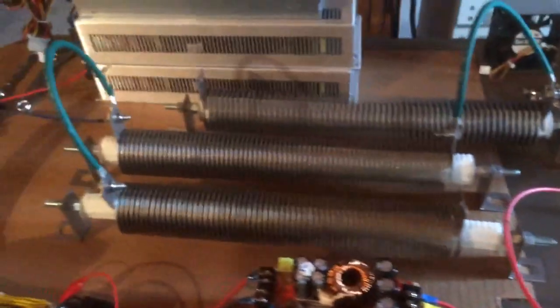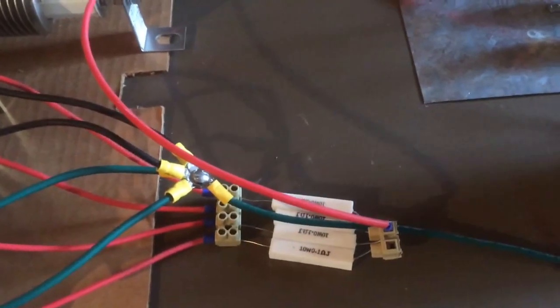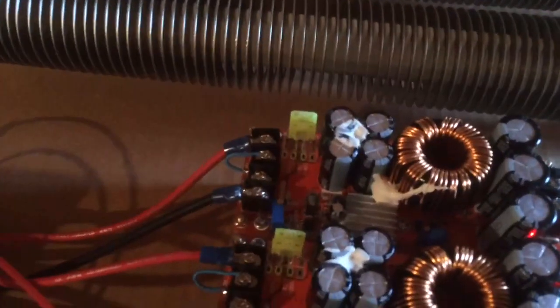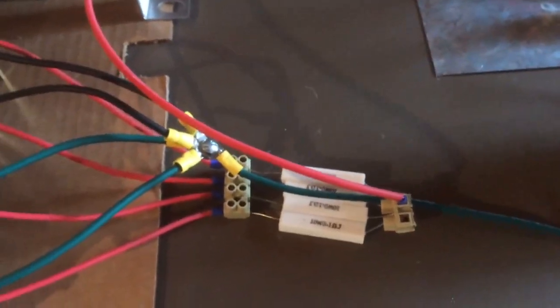That's really what needs to be done so that you don't overstress any one of the boost converters and or open the fuses. So that's the rationale behind testing it at a lower load getting it balanced and then connecting it to a higher load.